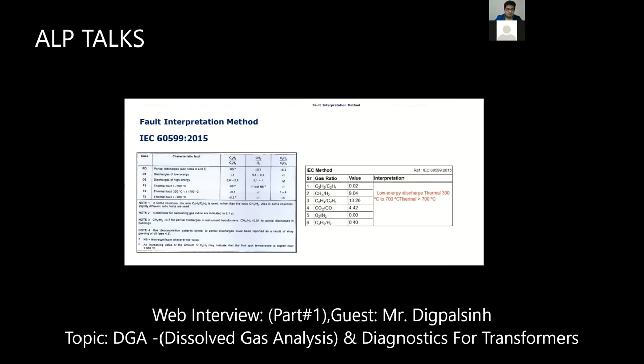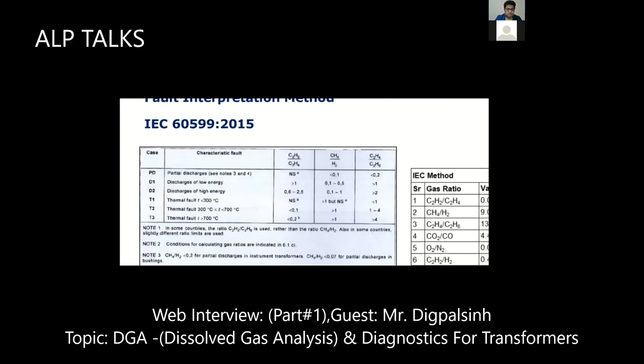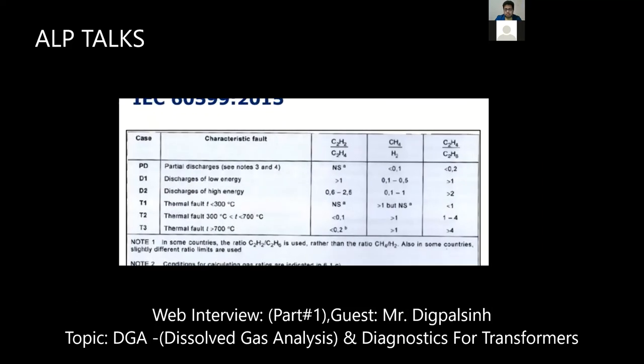So based on these three ratios, if you do DGA and take the ratios of these gases, you will find a chart like this. This I have cut and pasted from the IEC. The abbreviations we have seen previously are PD, D1, D2, T1, T2, T3. Based on the ratio values, you can categorize the fault. If the acetylene to ethylene ratio is greater than 1, CH4 to hydrogen is between 0.1 and 0.5, and C2H4 to C2H6 is again greater than 1, then you can say it is fault D1, discharge of low energy.